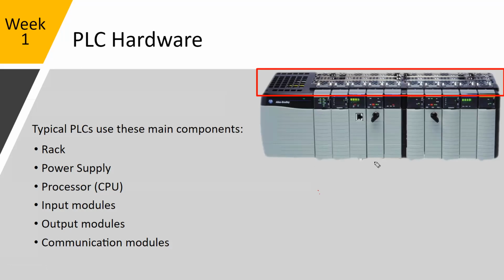So for this one, I had drawn here that these were your processors. You can identify that because of these keys. It's Allen Bradley. Some of them aren't doing keys anymore, but for the vast majority, you'll see this switch is to put the processor into different modes: run mode, program mode. We'll get into that later. This is just about being able to identify some of them. This portion of the rack is going to be your power supply, whether it be 120, 24 volts. Again, depending on your industry, you could actually get 24 volt AC or 120 volt DC.